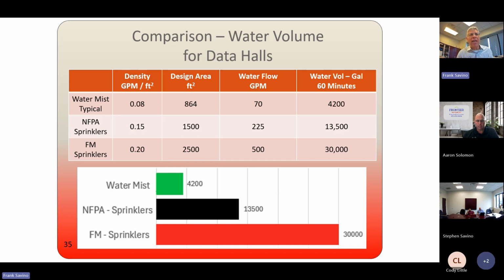So let's look at this table on the bottom. Water mist, 4,200, NFPA 13,500. Look at FM, 30,000. That's 7 times more water versus water mist. So that really graphically illustrates a significant difference between what you can do with water mist versus sprinklers.